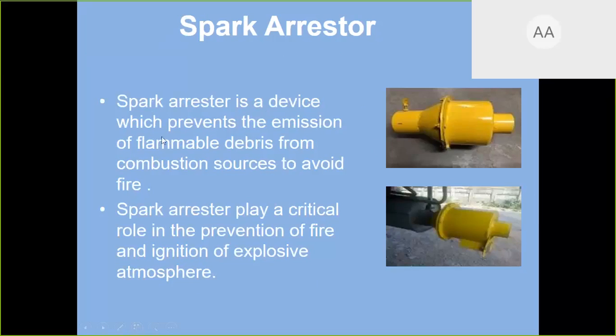It's a small device which prevents the emission of flammable debris from a combustion source. So whatever the combustion spark is, it will avoid going into the debris, the dust, the scrap, which has a calorific value, and that's why we call it flammable debris. It will avoid the ignition source going from the machine to this scrap, to avoid fire. It is very, very small equipment which can be installed in the duct and will prevent the spark. Spark arrestors play a critical role in the prevention of fire and ignition of an explosive atmosphere.